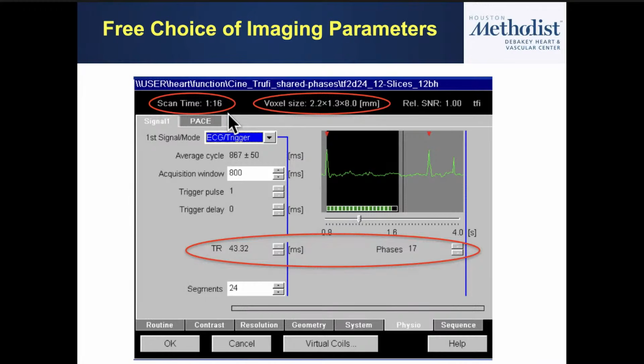And I'm going to go past this because we're going to talk about this a little bit more, which is what are the parameter settings that we use when we're trying to do either static or cine-based imaging. A few of the important parameters obviously are pixel size, where you have complete control over how high or how low resolution you want, and also frame rate or temporal resolution, and you have complete control over that. Now, obviously, to go to higher resolution, either spatially or temporally, is going to require more time and therefore a longer breath hold time. But you can adjust these as much as you want, and the scanner will actually tell you, based on the parameters that you've set, what the actual acquisition time is.